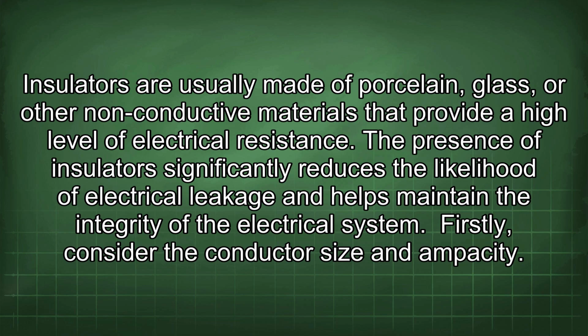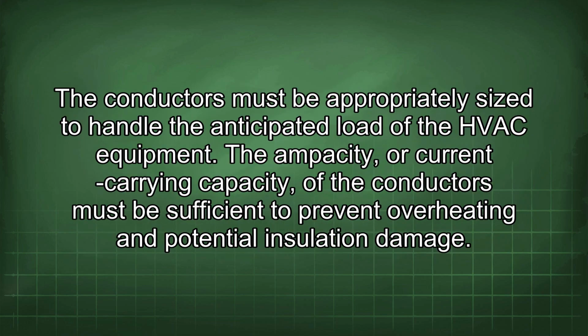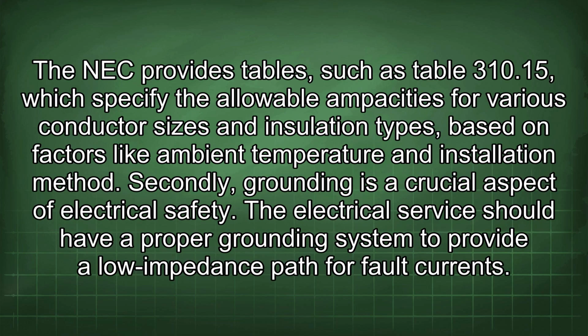Firstly, consider the conductor size and ampacity. The conductors must be appropriately sized to handle the anticipated load of the HVAC equipment. The ampacity, or current carrying capacity, of the conductors must be sufficient to prevent overheating and potential insulation damage. The NEC provides tables such as Table 310.15, which specify the allowable ampacities for various conductor sizes and insulation types, based on factors like ambient temperature and installation method.